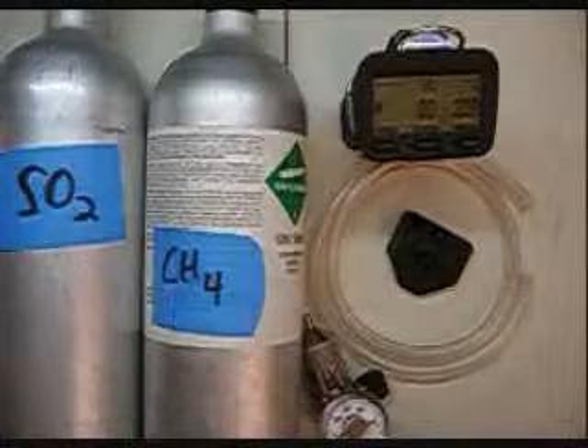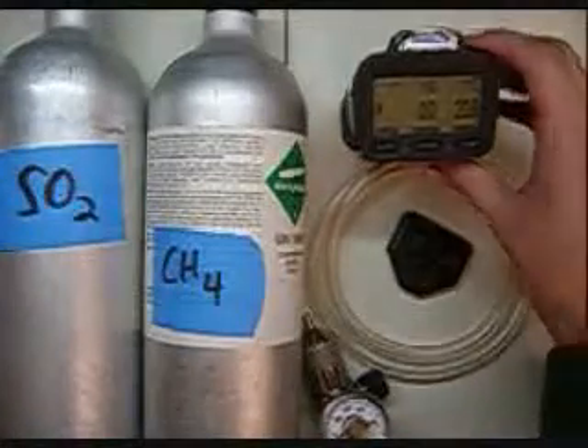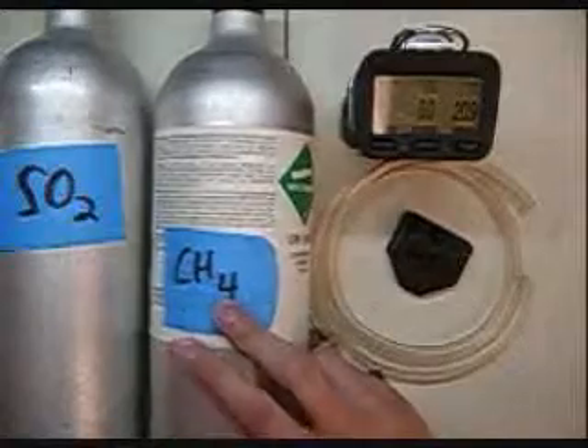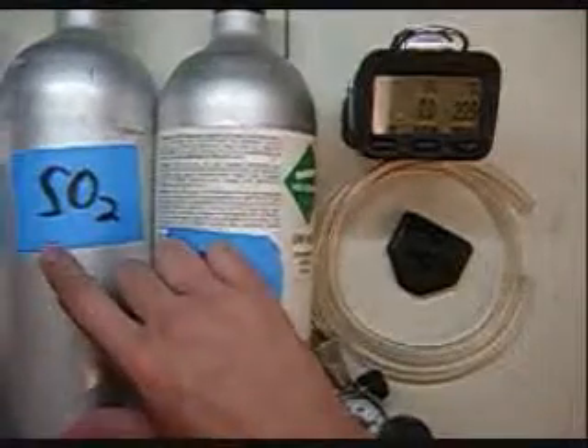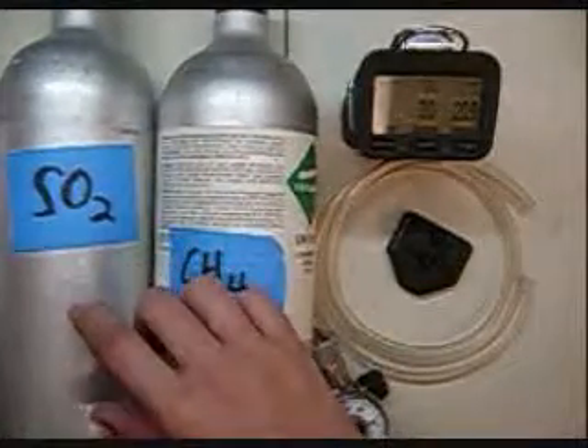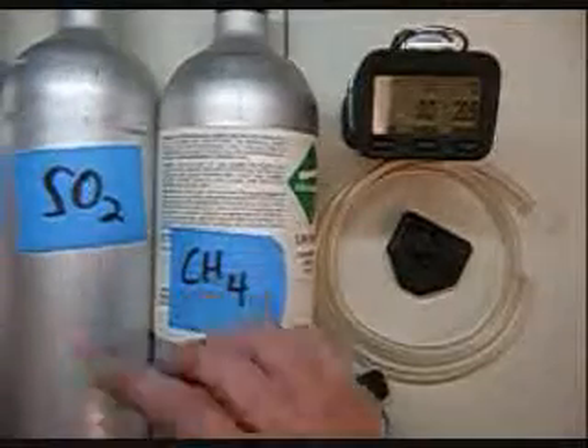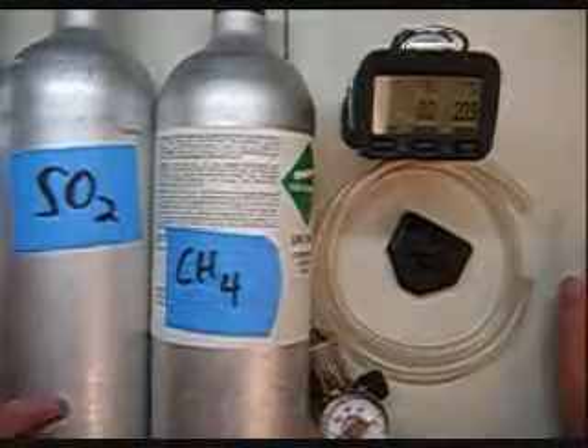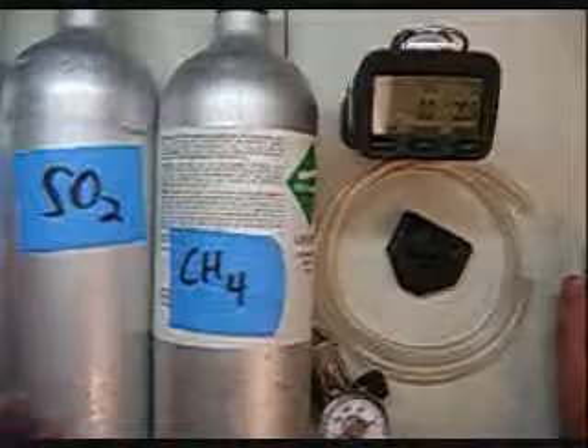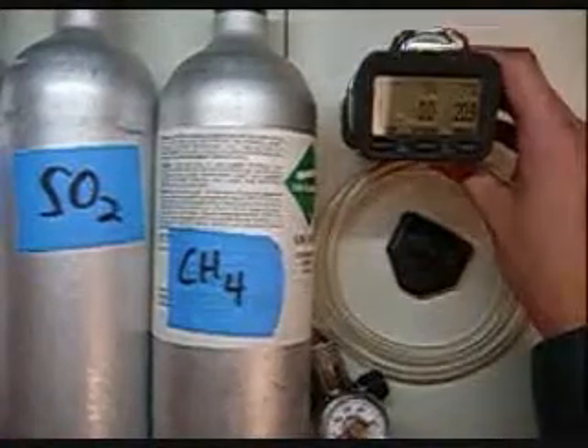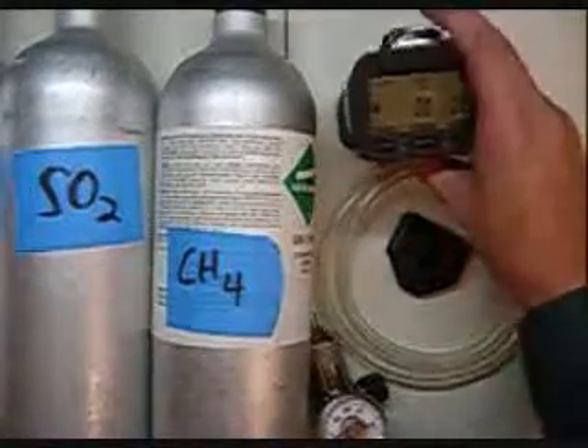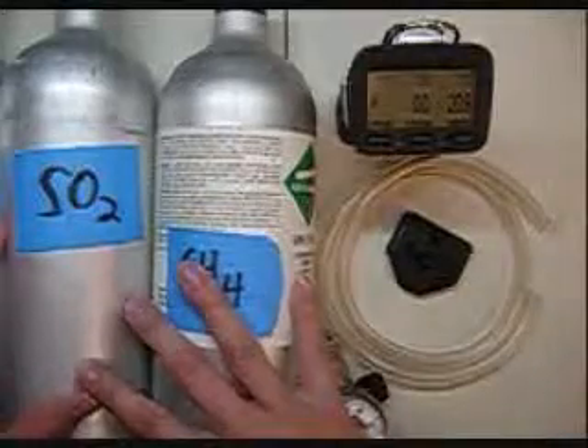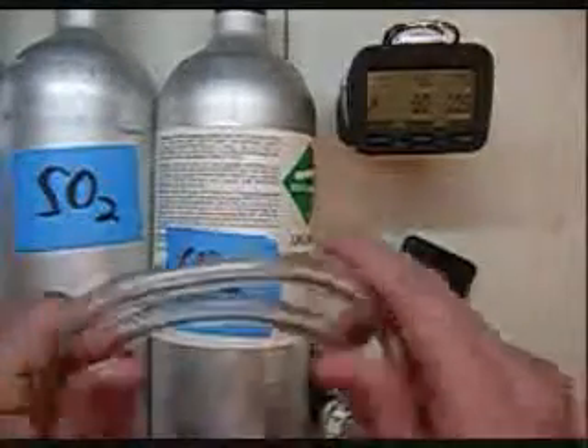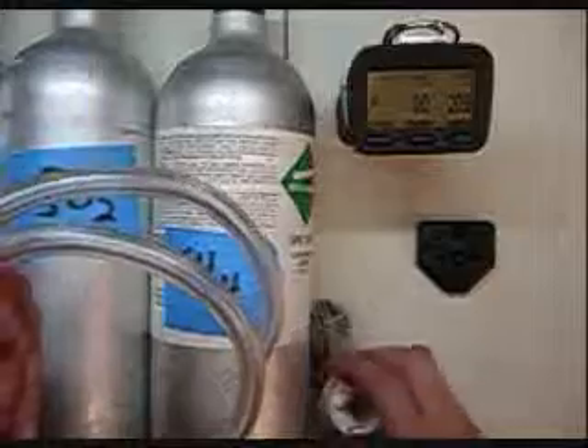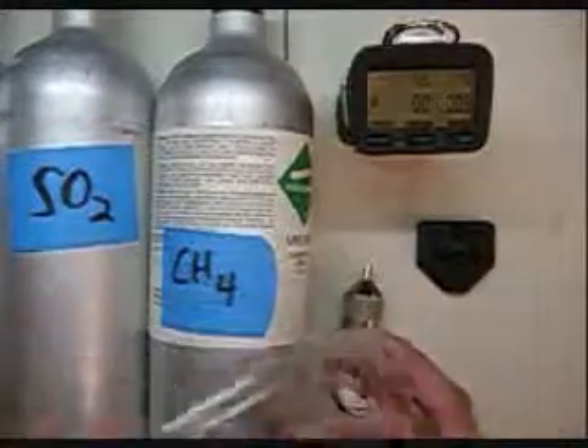Today we're going to be looking at the G460 that you have. It's going to have an oxygen, a methane, sulfur dioxide, and also an ammonia sensor in there. Now these gases have some interplay, so we're going to show you how to calibrate it without having any problems. What you're going to need first: the monitor itself, all 3 cylinders of calibration gas, some tubing, the cal cup, and a regulator, 0.5 liters per minute.